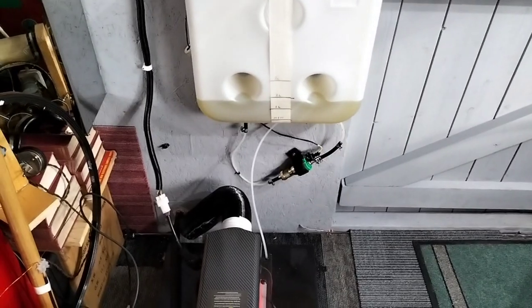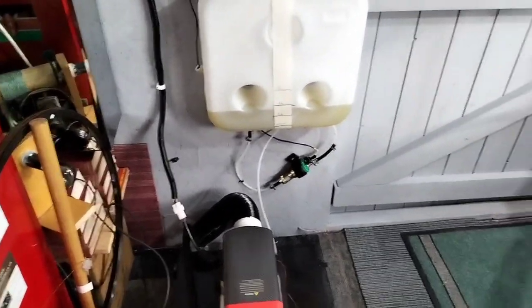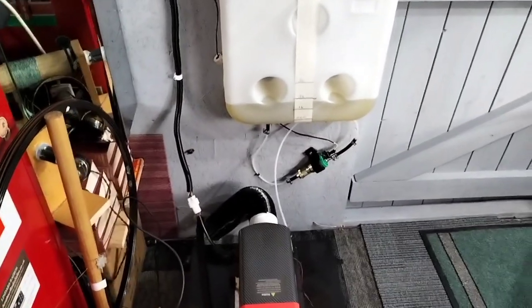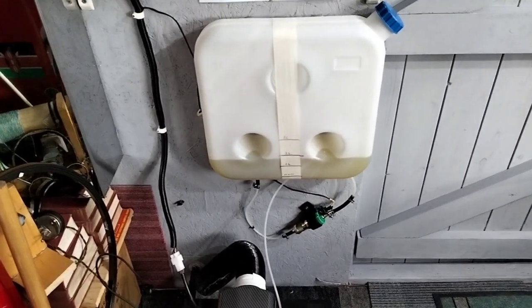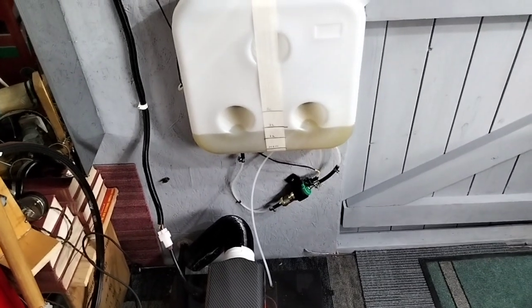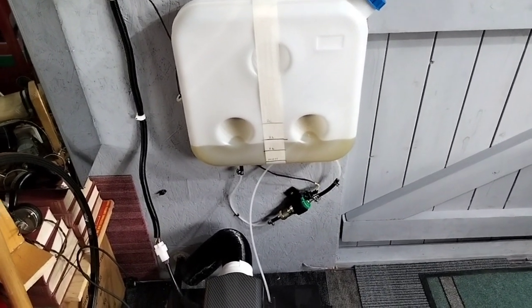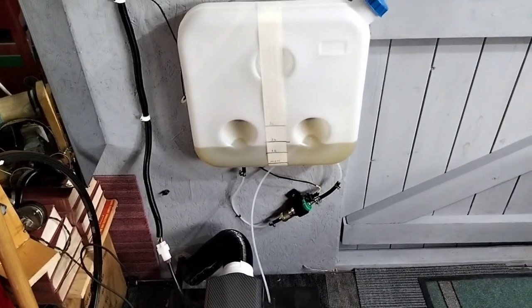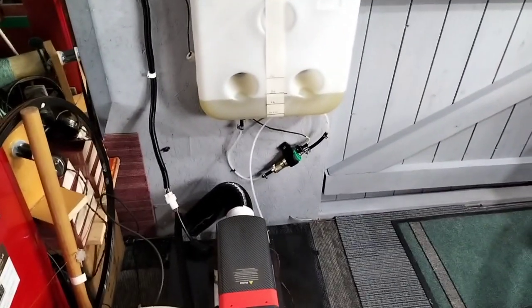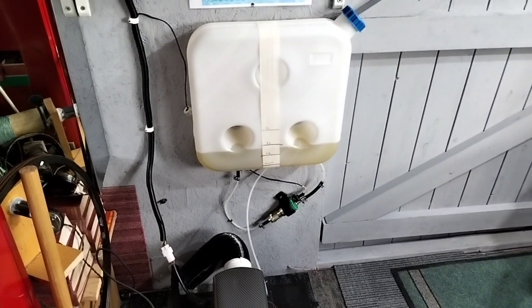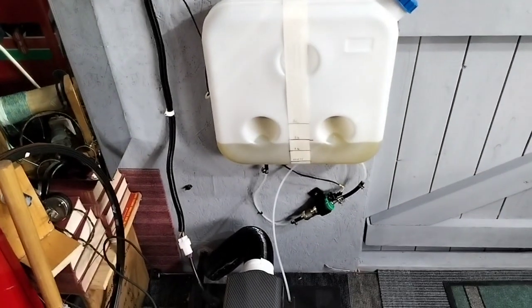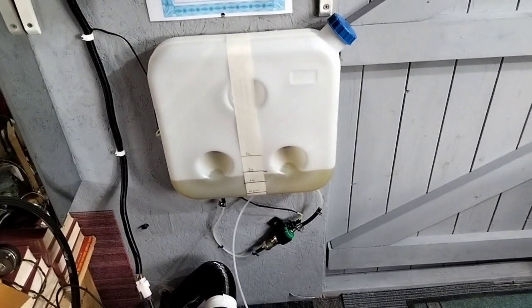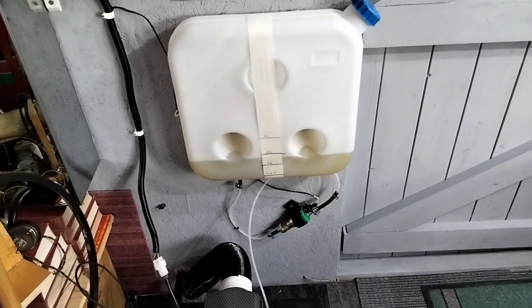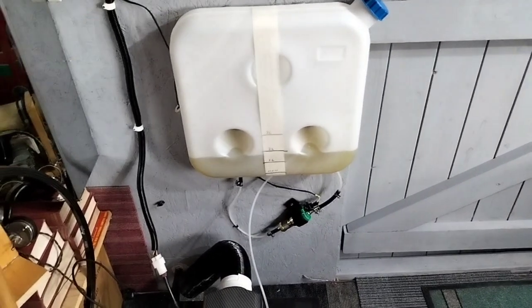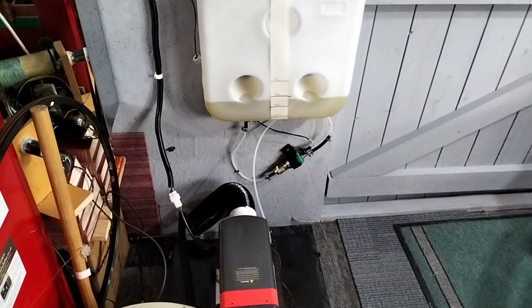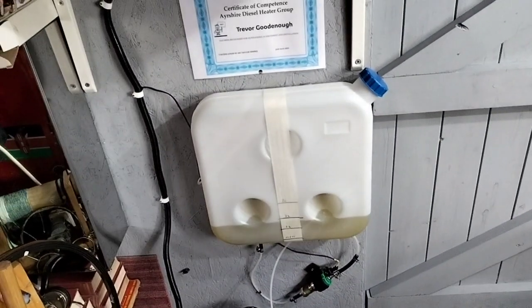I used to do pressure washer and steam cleaner repairs with diesel boilers in them, and they would soot up if the mixture was too rich, and also if it was too lean. A lot of people think it only happens when it's rich, but it happens if it's lean too, because you get incomplete combustion with a lean mixture. Fuel is left over and collects on the walls of the heat exchanger, burns up that way, and leaves a residue of soot. So you can get soot both ways. The idea is to aim for a low CO level if you can.